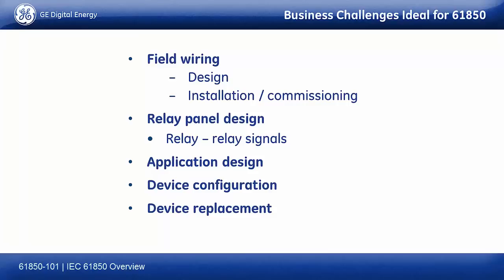So one of the things about microprocessor devices is they don't last 40 years like the primary equipment. They last 10 to 15 years and I have to replace them, right? So if I can make this replacement project easier, that also helps as well, right? So these are challenges that are ideal for 61850. The question is, should we do that?